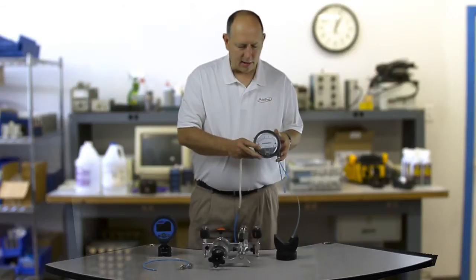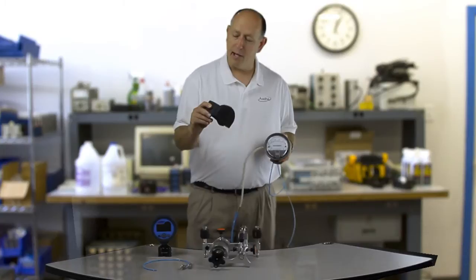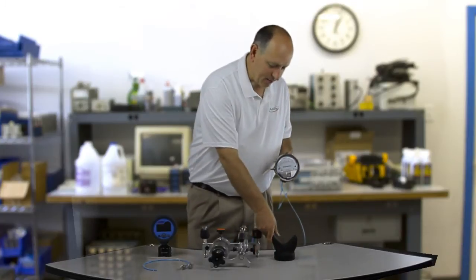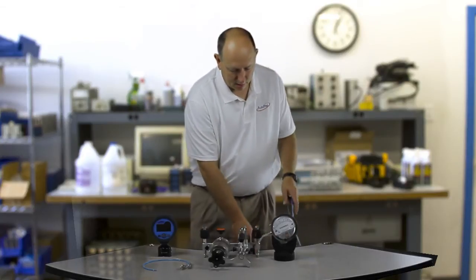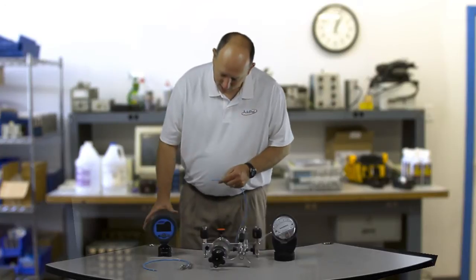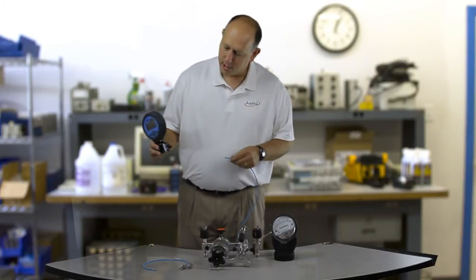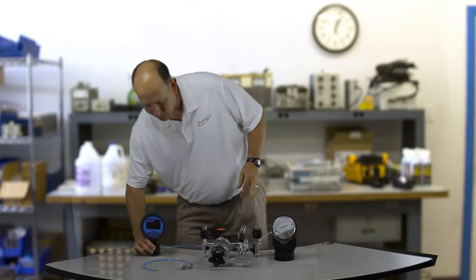By the way, Magnehelic gauges need to be calibrated in the upright position. That's why I have this little Pac-Man looking tool here — we actually make that and include it with this kit. So I'm going to put that on the low side of the Magnehelic and tie it into the low side of the reference gauge. Those two low sides are now tied together.